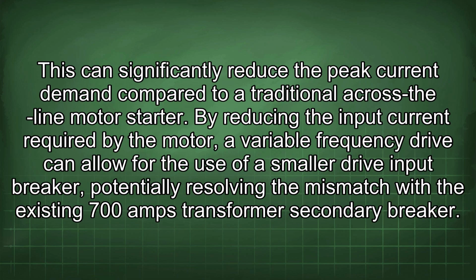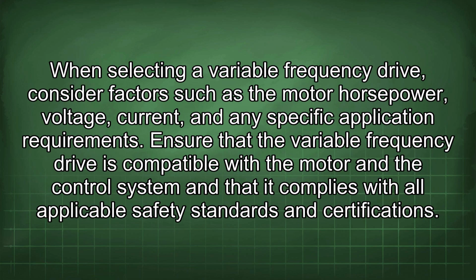This can significantly reduce the peak current demand compared to a traditional across-the-line motor starter. By reducing the input current required by the motor, a variable frequency drive can allow for the use of a smaller drive input breaker, potentially resolving the mismatch with the existing 700 amps transformer secondary breaker. When selecting a variable frequency drive, consider factors such as the motor horsepower, voltage, current, and any specific application requirements. Ensure that the variable frequency drive is compatible with the motor and the control system, and that it complies with all applicable safety standards and certifications.